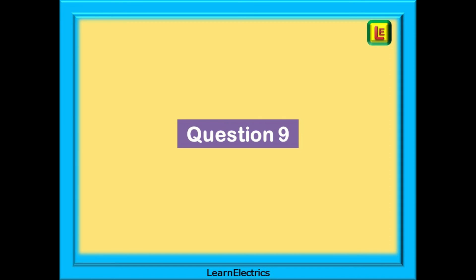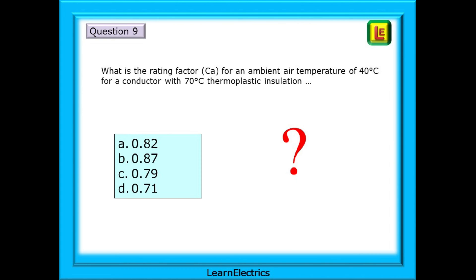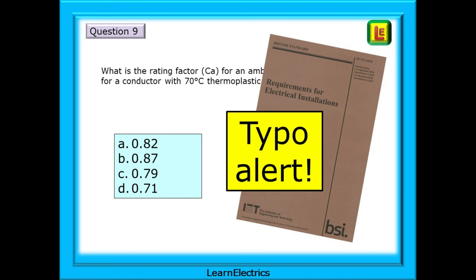Moving on, we have question number 9. What is the rating factor CA for an ambient air temperature of 40 degrees Celsius for a conductor with 70 degree thermoplastic insulation? But hold on before you dash off to find the answer. There is a typo in some of the wiring regulations books. Some of the brown books have been printed with an error which we can sort out right now.